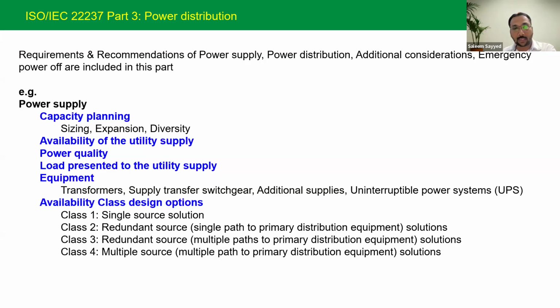Once it comes into your premises, you need to check the energy part of it. How are you going to do the energy metering? You have to have a summation meter to measure the energy, a dual source meter. Those are all challenges you need to tackle. Most utility companies across the globe, especially in developing countries, don't have dual supply in the same premises. They don't have a summation meter kind of setup. But you need to deal with all those scenarios.